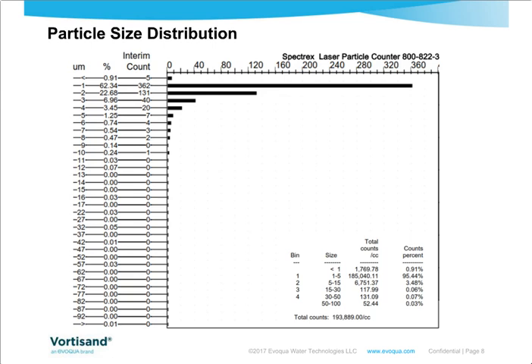This is an example of a laser particle count analysis showing your particle size, which is represented by the vertical axis, in microns, from less than 1 all the way up to 100. The black bars that go horizontally represent the count of particles at different sizes. So in this example, over 95% of the particles are less than 5 microns in size. That's very important information to know when you are looking at the quality of your water sample. You need to understand not only the TSS, but also what sizes the particles are.